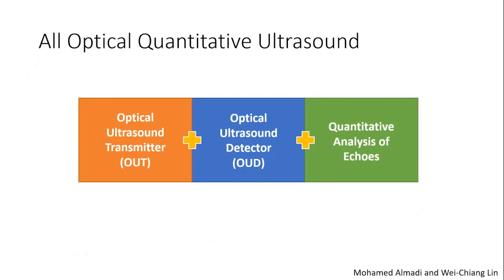Some of you probably have taken Dr. Makura's and my imaging courses, so you know what ultrasound is, right? To create all optical quantitative ultrasound, you have to have 3 elements. You have to have an optical transmitter, I call it OUT, and an optical ultrasound detector, OUD, and then you also perform quantitative analysis of echoes. Typically in ultrasound imaging, echoes are analyzed according to the intensity. We call that echogenicity. And we feel like we can do more than that.